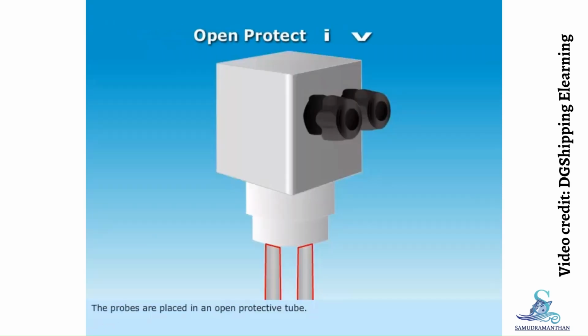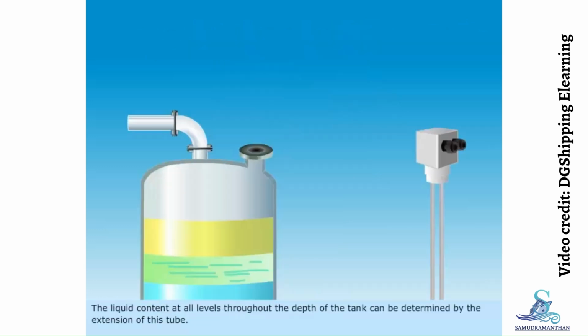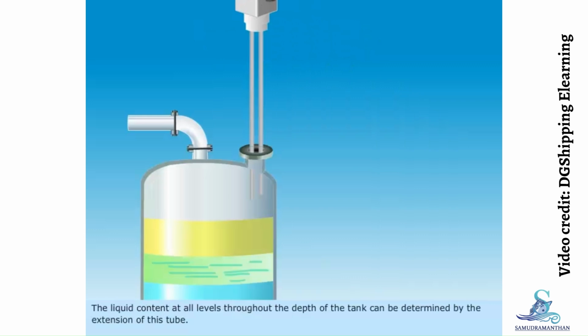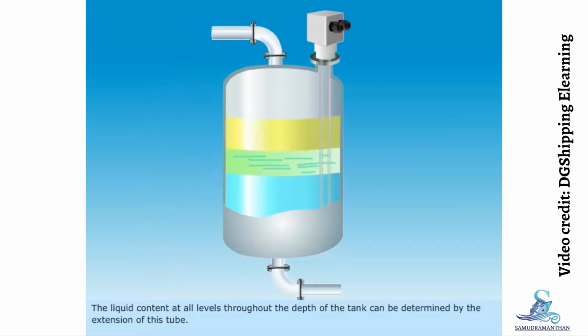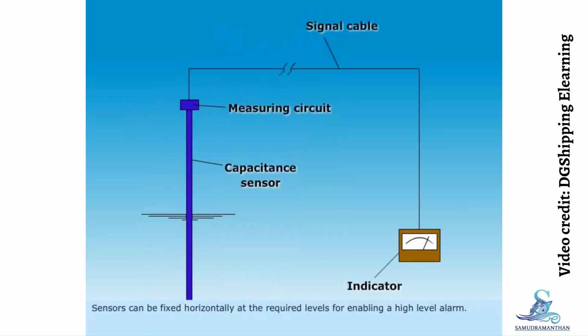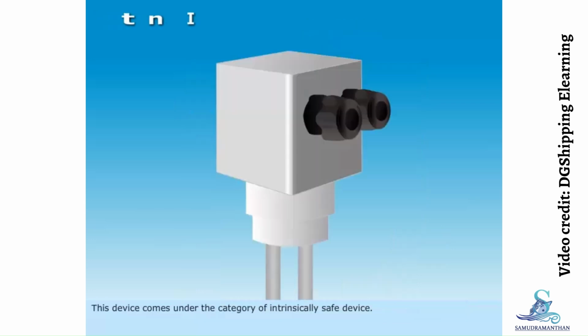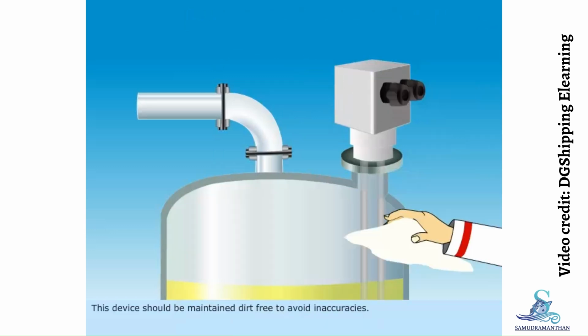The probes are placed in an open protective tube. The liquid content at all levels throughout the depth of the tank can be determined by the extension of this tube. Sensors can be fixed horizontally at the required levels for enabling a high-level alarm. This device comes under the category of intrinsically safe device. This device should be maintained dirt-free to avoid inaccuracies. Thus, you have learned about the capacitance gauge.